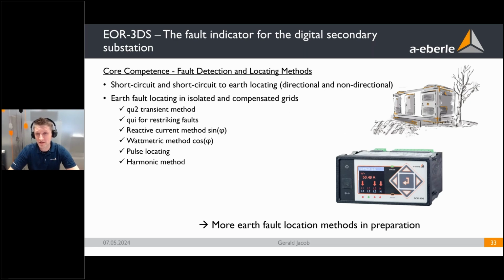Yeah, our core competence of the device EOR-3DS, of course, is the fault detection and location. We have the same algorithms on board as the EOR-1DS and even some more, because the device is not microcontroller based, but a Linux based device with more resources and capabilities. So compared to the EOR-1DS, the device also has the QU2 transient method, which is very reliable and always used, but can only be used when the Earth fault begins, and has in addition the QUI for restriking faults, which is not available in the EOR-1DS. So for cable networks, this is quite useful.